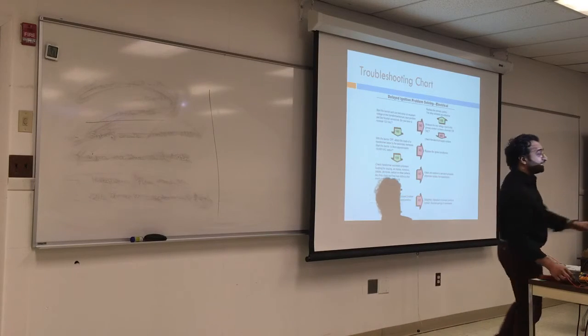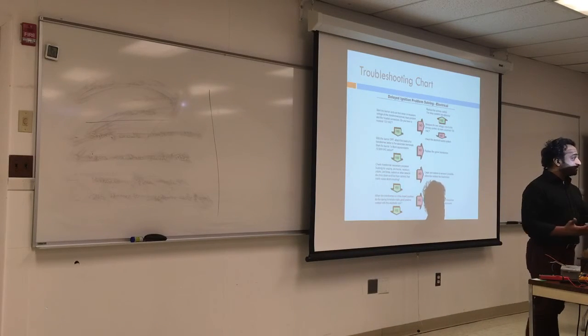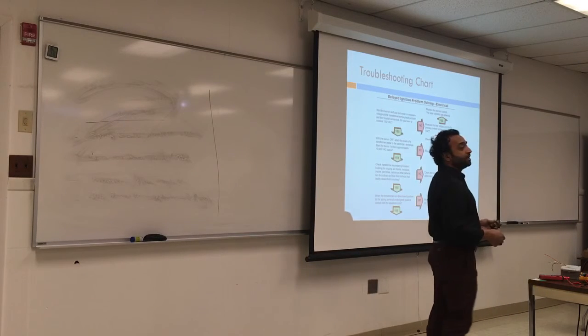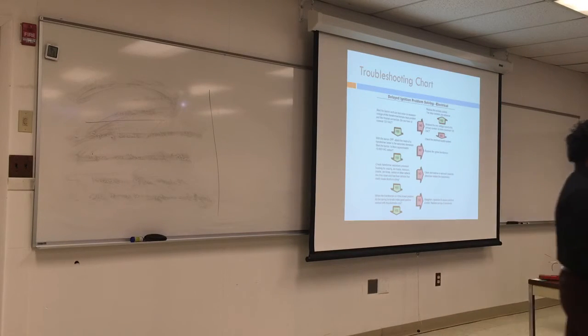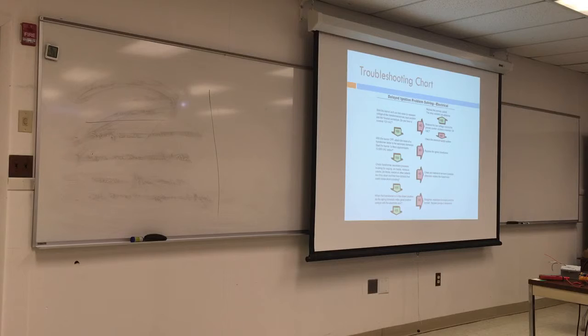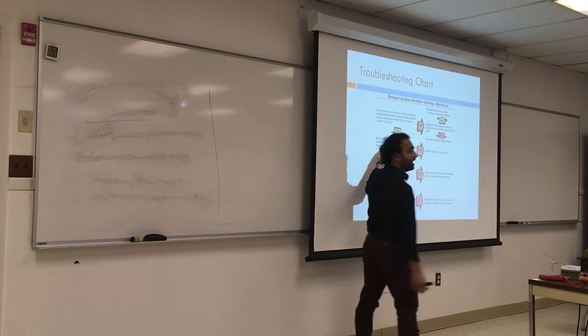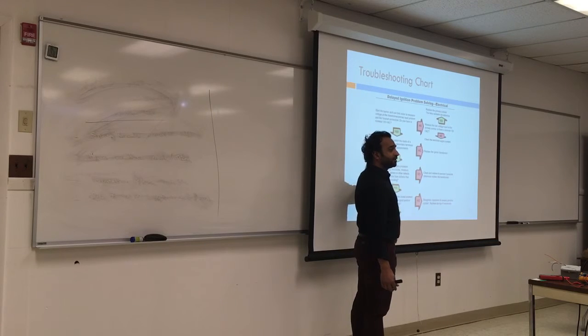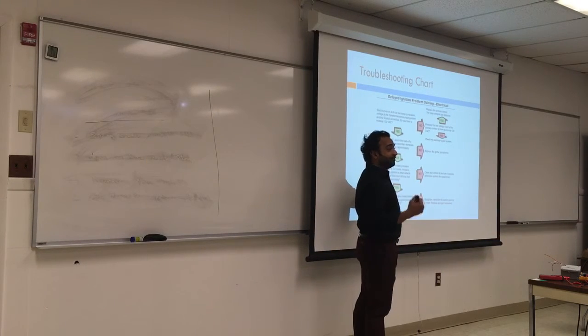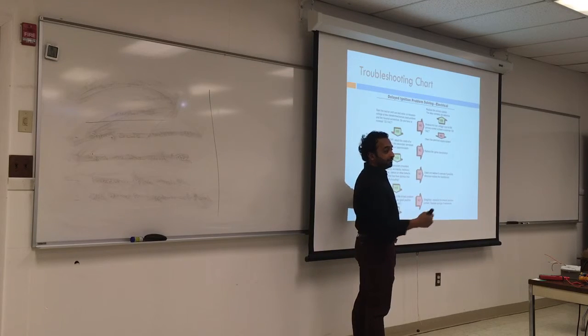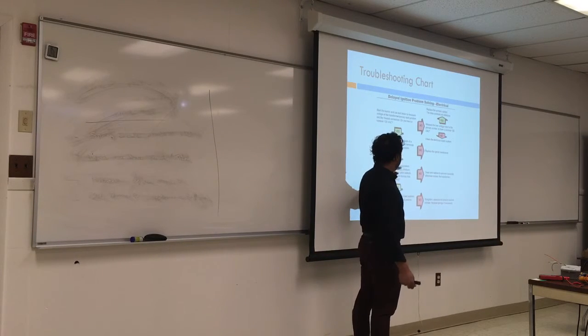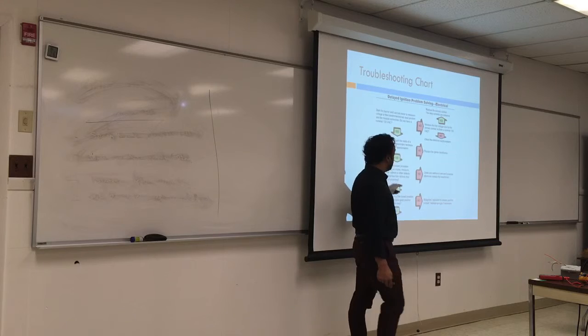So this is assuming you have a tester with you. You're going to put the tester on and make sure you have 10,000 volts. If you don't have a tester, you're going to do the other thing. Test the resistance, test for colors. This step is just to know that you have 10,000 coming out of the transformer. So we have 120 coming in, 10,000 coming out. Yes or no? Yes. Move on to the next step.